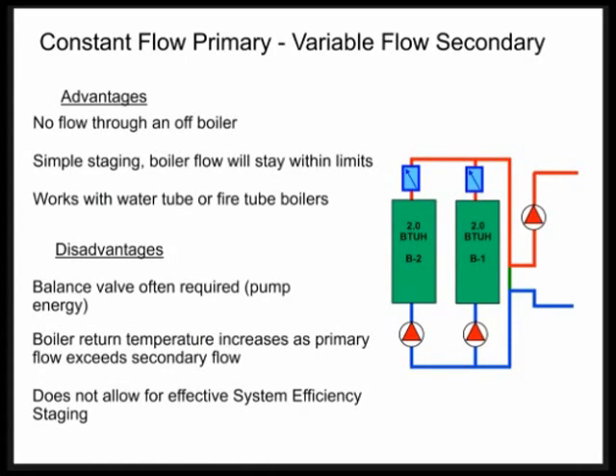The advantages being there's no flow through an off boiler. There's simple staging. Boiler flow will always stay within its limits. Some of the advantages, no flow through an off boiler. Whenever you cut a boiler off, the pump goes off. So you don't have those stack losses that can happen on a boiler when you have flow rate going through the boiler and it not running. Simple staging. The boiler is always going to stay within its flow limits. You don't have to worry about two pumps running through a boiler or a pump only going half flow through a boiler. You just nice, simple, turn the boiler on, the pump comes on, turn the boiler off, the pump goes off. Another advantage is that this system, this layout will work with water tube or fire tube products. It works great with condensing. It works great with non-condensing. You can apply just about any product in constant flow primary or variable flow secondary.